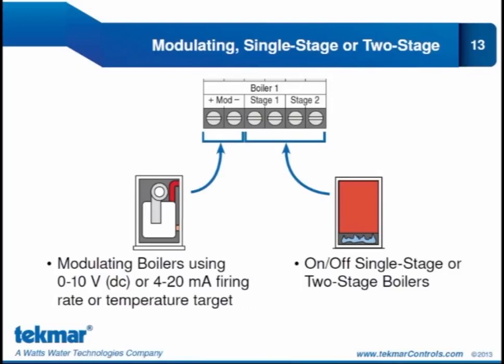There are 4 boiler banks, and each bank has 6 terminals. We have our modulating plus-minus terminals, our stage 1 terminals, and our stage 2 terminals. If we are operating a modulating boiler, we will connect to the mod plus-minus terminals. If that boiler also needs an enable, we will connect to the stage 1 terminals as well.